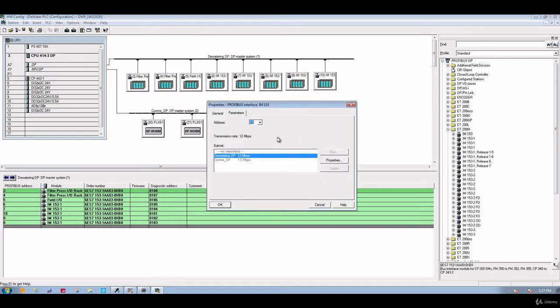And then add new one. Okay, now I'm adding a new one. It asks me for the Profibus address. All the addresses here are in sequence, 3, 4, 5 up to 10. I'll put the next address. It gives me 11, 12, 13, 14 up to 125. I can put up to 125 remote I/Os.